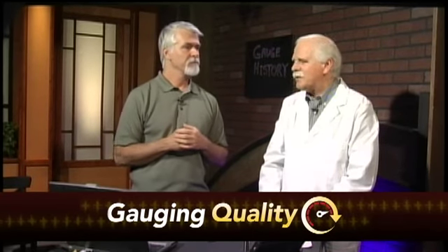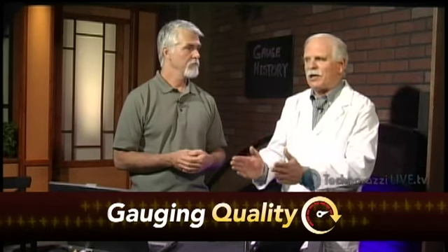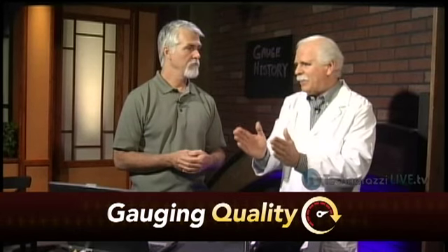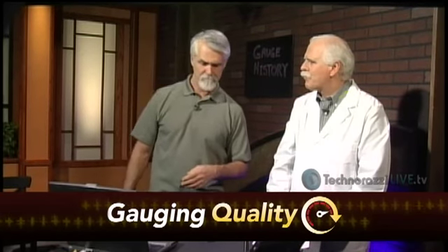Okay, all right. But yes, a lot of people will do an interval extension, and that's a great use of calibration history, and that's where this can help. You can look and see you've never had to adjust that gauge. It's a micrometer standard. It's always measured the same amount. It's not growing, it's not shrinking, it's not wearing. It would be valid to do it based on that. It's a great question. All right. Any more questions, Chris? Okay.